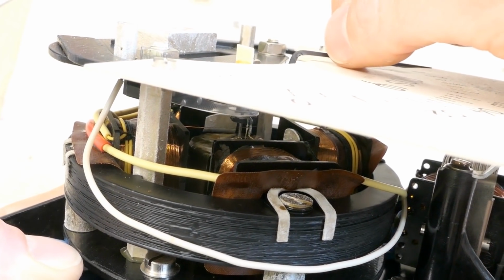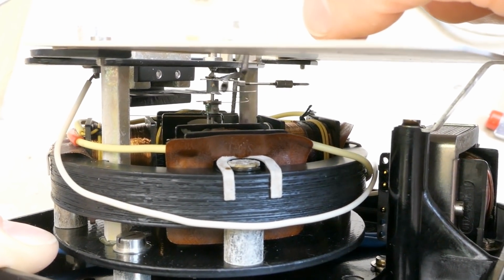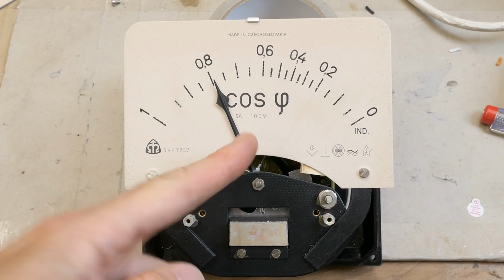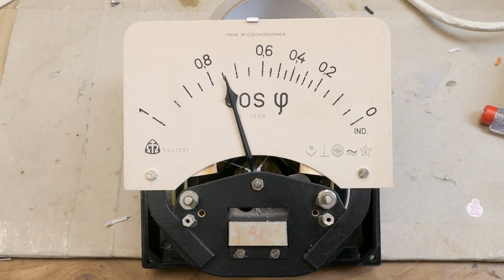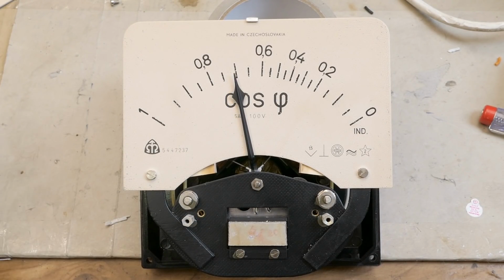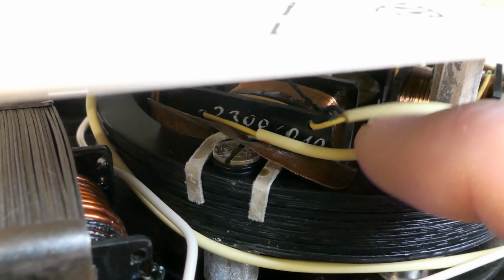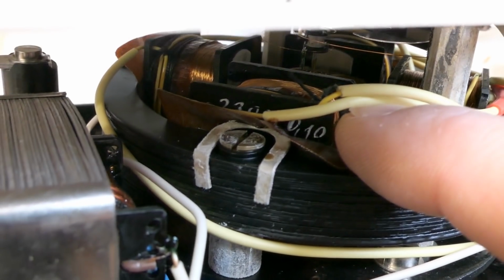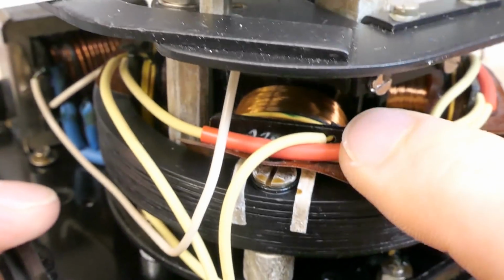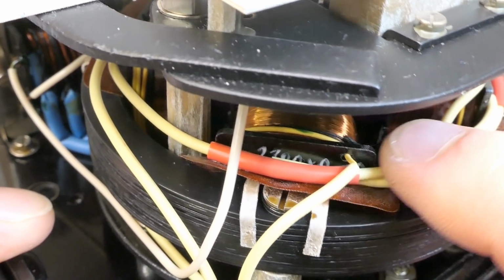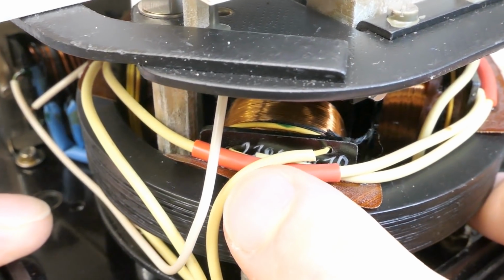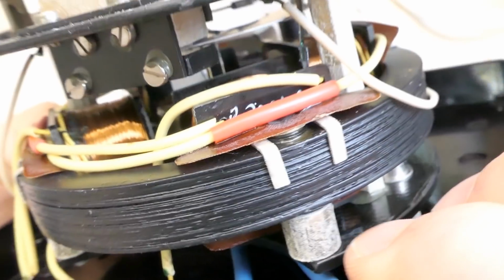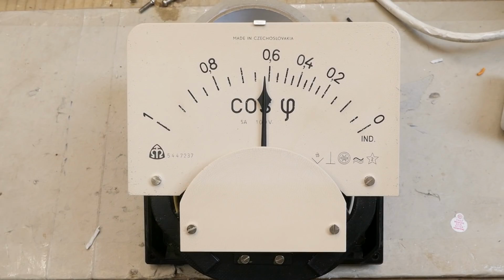That's basically it. Now can I somehow power it? It says 5 amps for the current sensing, but I don't know how the voltage coils are meant to be connected. And the coils have some marking. It looks like 2300 turns, 0.1 millimeter diameter. And all four have the same probably. 2300 turns, 0.1 millimeter wire. And this is a 3-phase version, not a single-phase version.